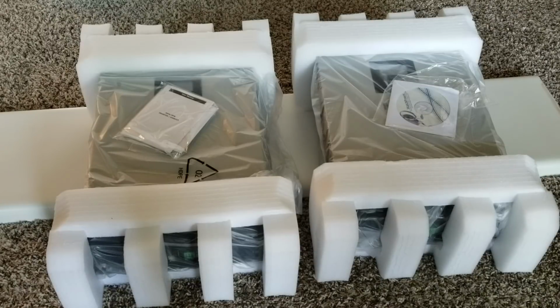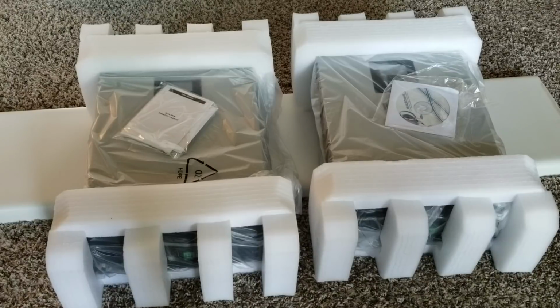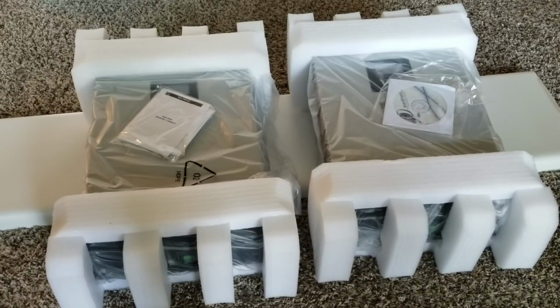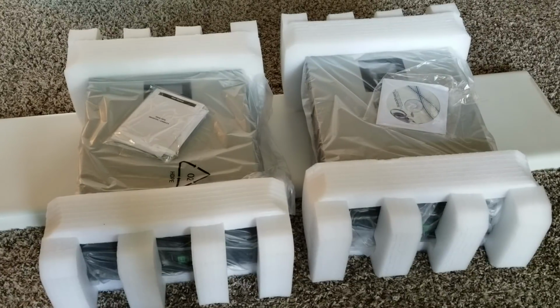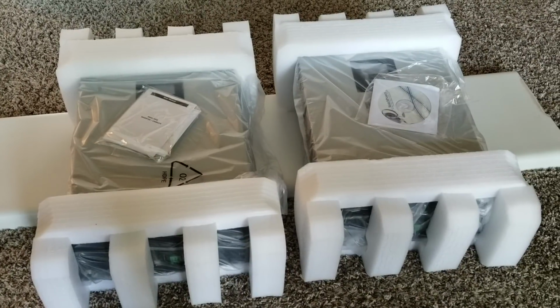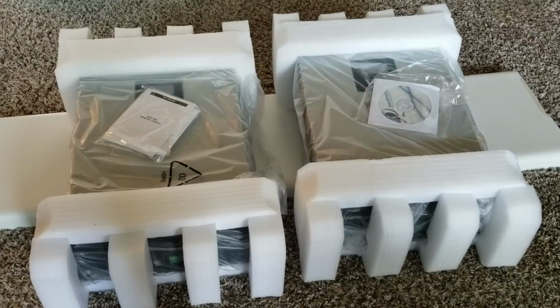If you wire your solar panels, make sure for this device, the open circuit, the VOC - that's the sign for open circuit. Your solar array's max PV array open circuit, the VOC, is supposed to be approximately or exactly 450 volt DC. If you pass this range, sometimes if you get too close to this range, your inverter won't work. It won't recognize this because the voltage is too high - you've already hit the high threshold, way beyond the specification of this device.